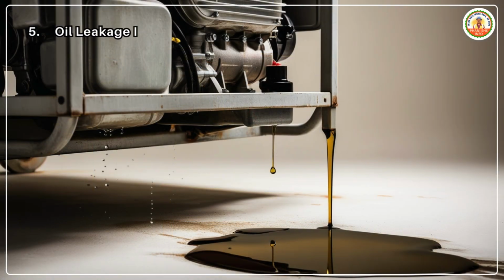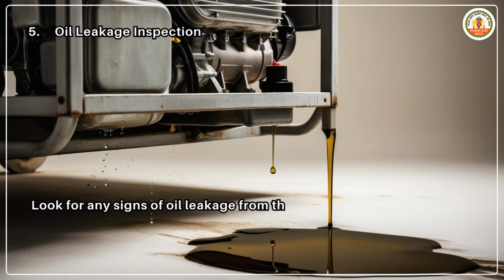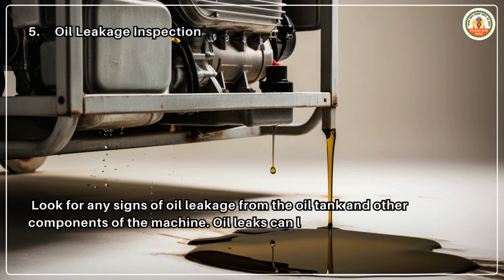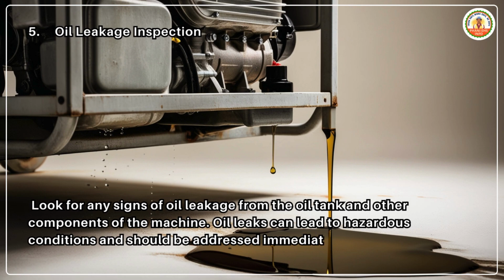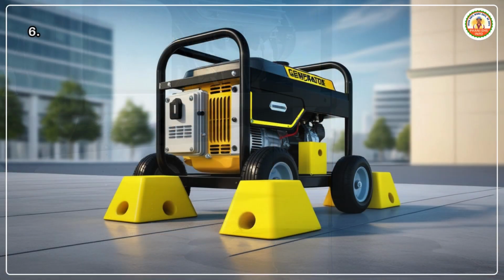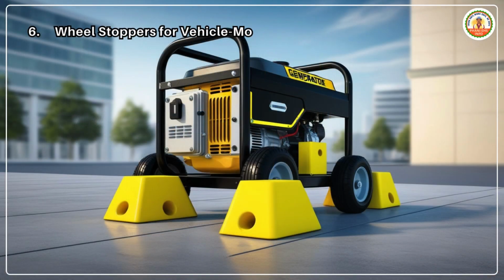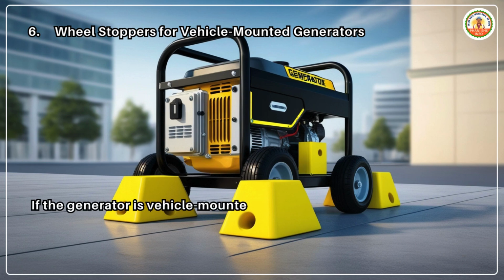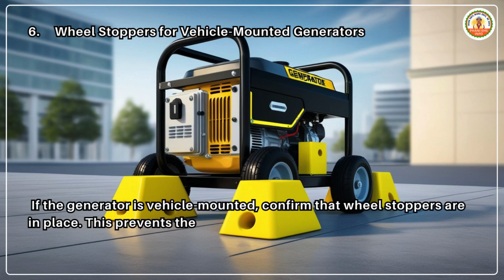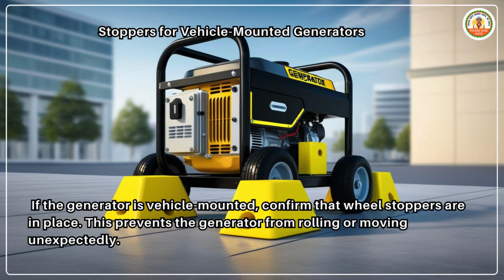5. Oil leakage inspection. Look for any signs of oil leakage from the oil tank and other components of the machine. Oil leaks can lead to hazardous conditions and should be addressed immediately. 6. Wheel stoppers for vehicle-mounted generators. If the generator is vehicle-mounted, confirm that wheel stoppers are in place. This prevents the generator from rolling or moving unexpectedly.